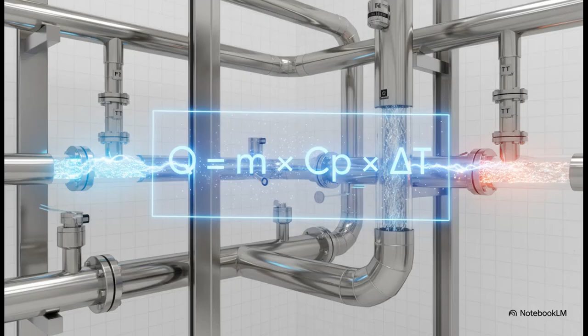At the core of everything is this fundamental physics equation. Don't let the letters scare you, it's actually pretty simple. It just says that the cooling energy delivered, which is Q, depends on two main things: how much water is flowing, that's M, and how much that water's temperature changes along the way, that's delta T. This simple formula governs the entire system.